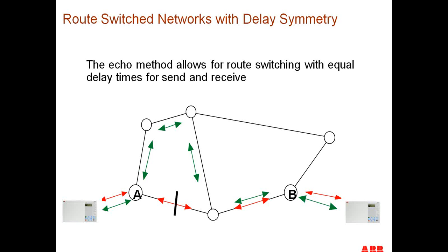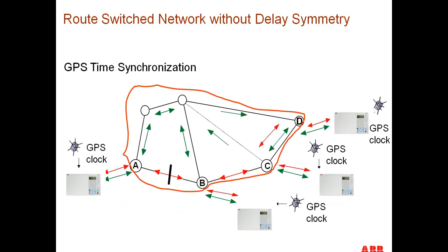Dissymmetry you can allow before the relay doesn't work properly. So modern relays, instead of using echo timing, put a GPS time synchronized signal at each terminal. Using a GPS clock at each terminal, each of the samples is time tagged by the GPS clock, so that when it gets to the remote end, it doesn't care how long it takes to get there. It's time tagged so it knows exactly how to line it up with the remote end. So it's very easy. So it's recommended that anybody.